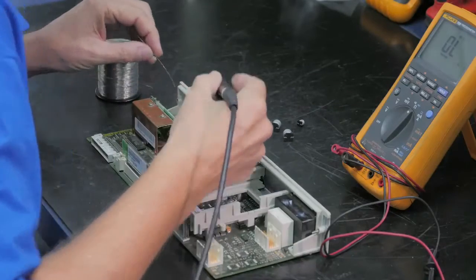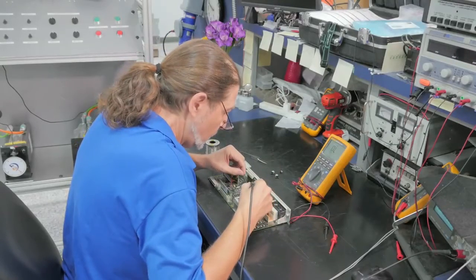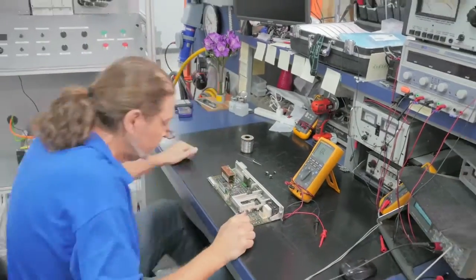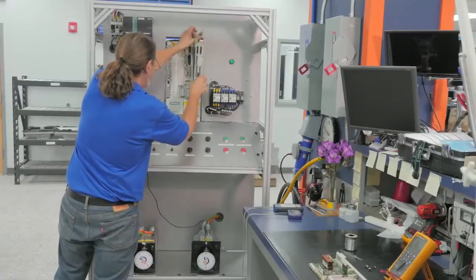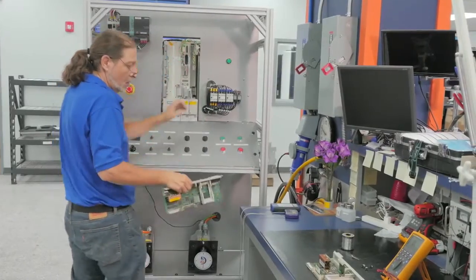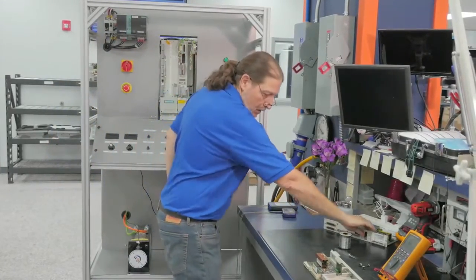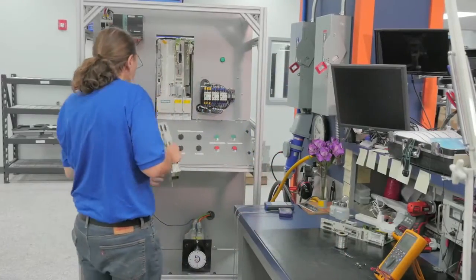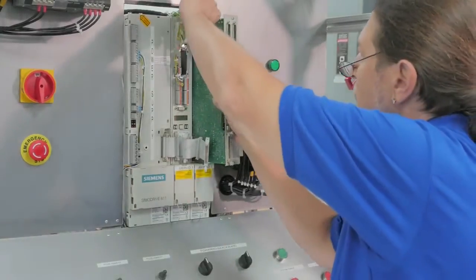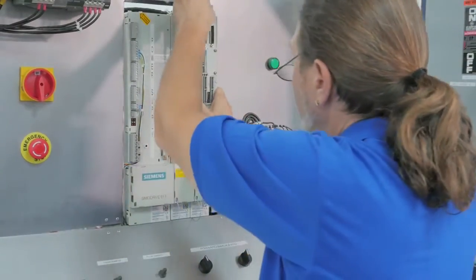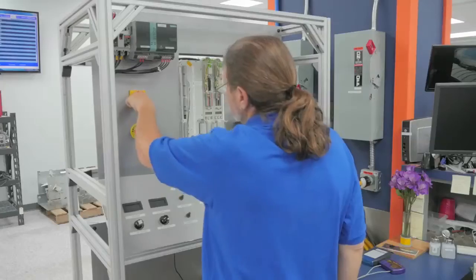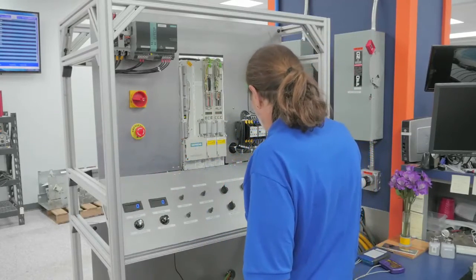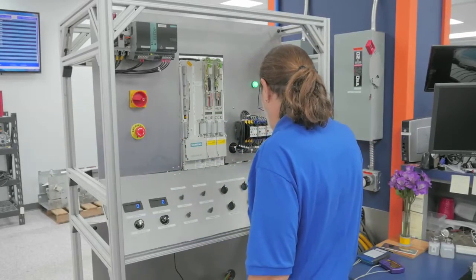After the technician has finished changing out the capacitors, he will now load test in our Siemens SimoDrive test stand. First, he will remove the known good servo card and then replace with the customer's servo card to see if changing out the capacitors has resolved the power supply issue.